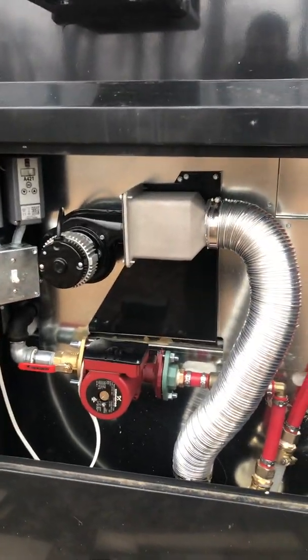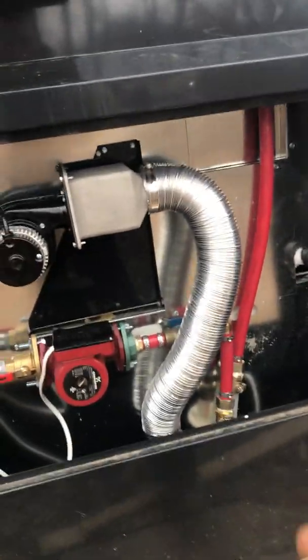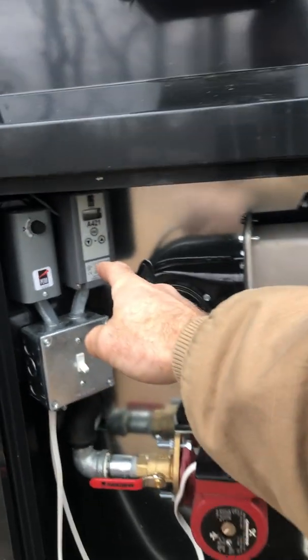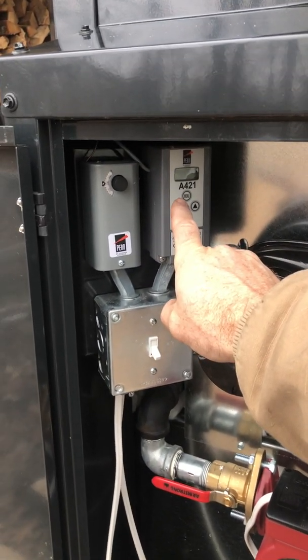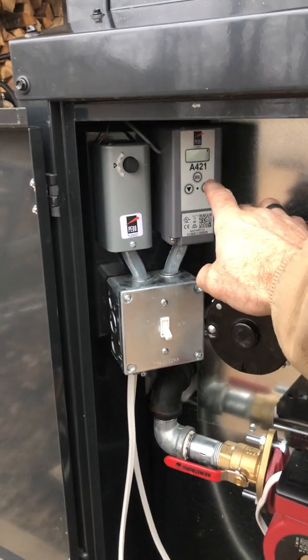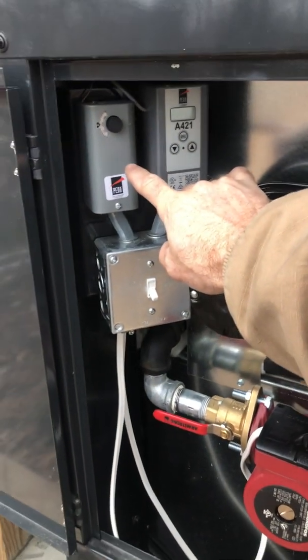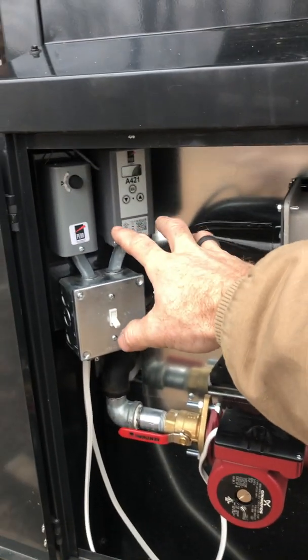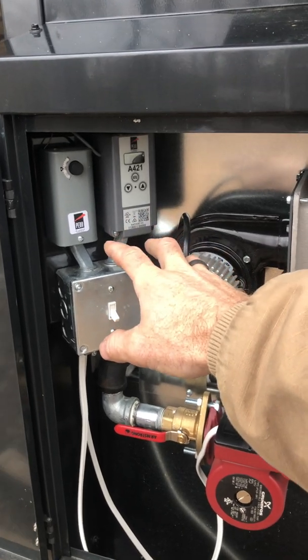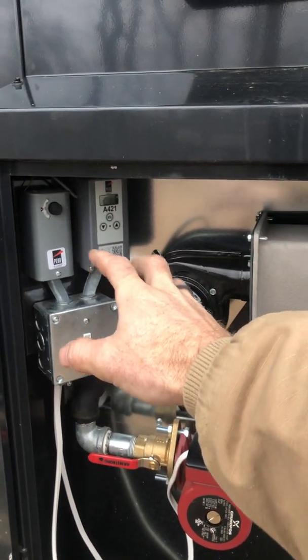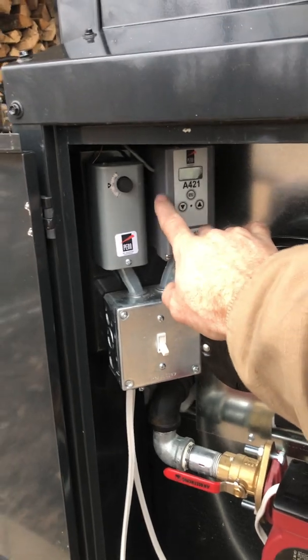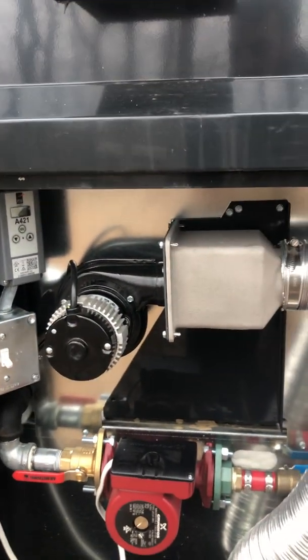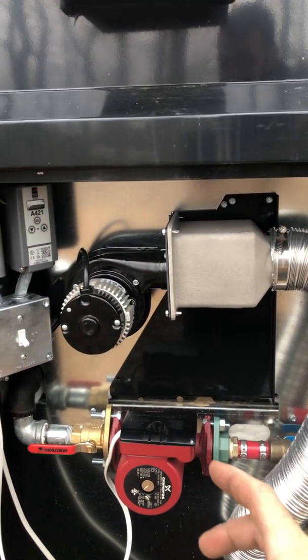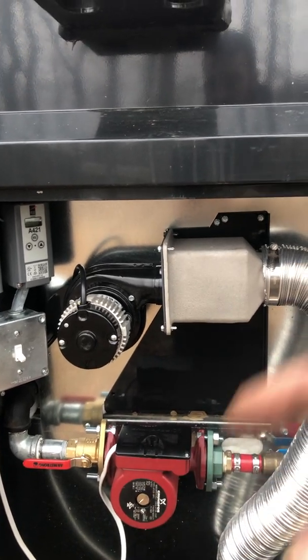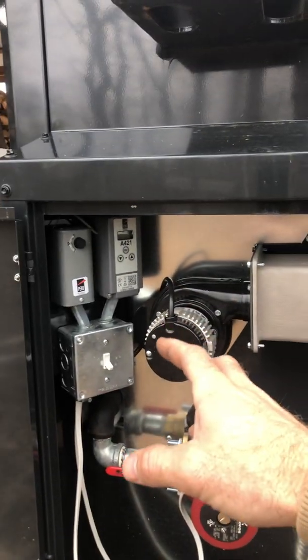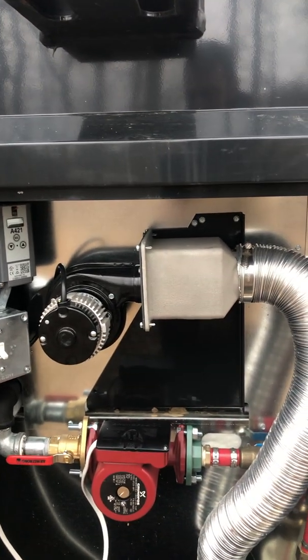So when the system does call for heat in the aquastat, this is the A421 Johnson Controls, and then the backup right here. These controllers you can get at any Grainger, pretty much any HVAC supplier. I think they're mostly used for things like walk-in refrigerators and freezers, but they do work well in this scenario. I'm using this one that's on the unit, and I actually have another one in the house, and I'll show you that too.